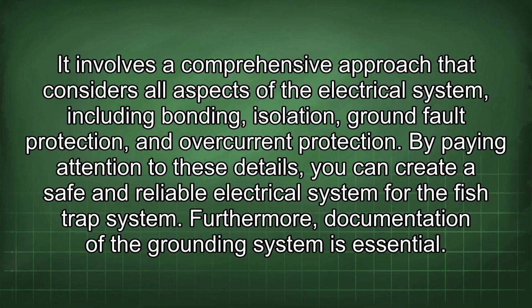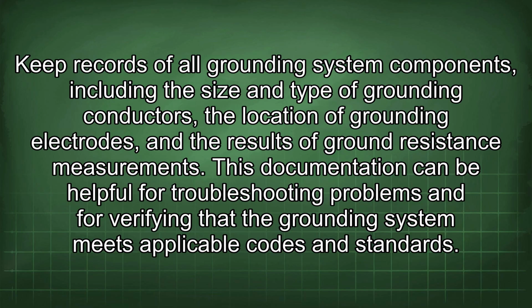Furthermore, documentation of the grounding system is essential. Keep records of all grounding system components, including the size and type of grounding conductors, the location of grounding electrodes, and the results of ground resistance measurements. This documentation can be helpful for troubleshooting problems and for verifying that the grounding system meets applicable codes and standards.